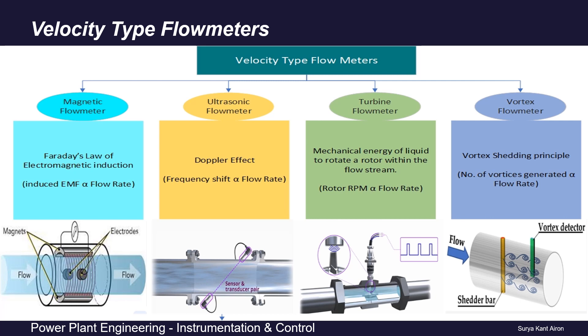The second type is ultrasonic flow meters that utilize the Doppler effect — the variation in sound frequency is calibrated to calculate fluid velocity. The third type is turbine flow meters, in which the mechanical energy of fluid is used to rotate a rotor placed in the fluid path; the RPM of the rotor is measured using a proximity switch, and this RPM is proportional to fluid velocity. The fourth type is vortex flow meters, where an obstruction called a vortex shedder is placed in the fluid path, generating vortices detected by a vortex detector.